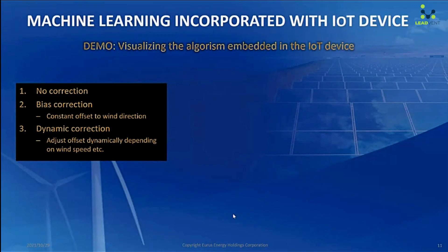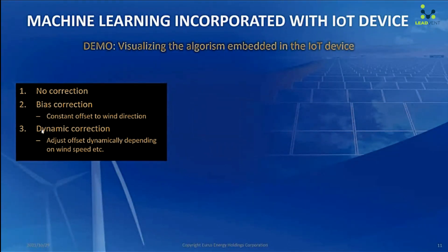I'm going to show the demo. The demo shows three defined modes. One is no correction. Number two is bias correction, where I correct a constant offset to the wind direction. Number three is dynamic correction, which adjusts the wind vane signal in real time depending on air temperature, wind speed, and nacelle direction.